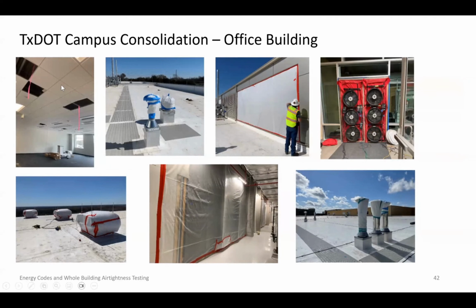So in these tests, suspended ceiling tiles, and if you have a UFAD, computer floors, are removed at a rate of about 1 per 500, and also a minimum of 1 per room, because we have to connect all the building. Remember, there can be no difference greater than 10% between the two furthest or most remote points in a building. And you see the louvers, you see exhaust fans. Here's the interior. There's the ceiling blower door fans being set up.